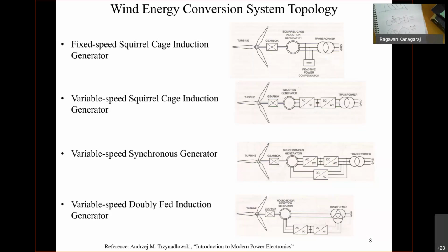Only thing is, there is some requirement to be met. If you want to achieve reverse power flow, there has to be active sources on both sides, only then reverse power flow is possible. Whereas reactive power, you can do even without an active power source, by suitably adjusting with pulse width modulation.